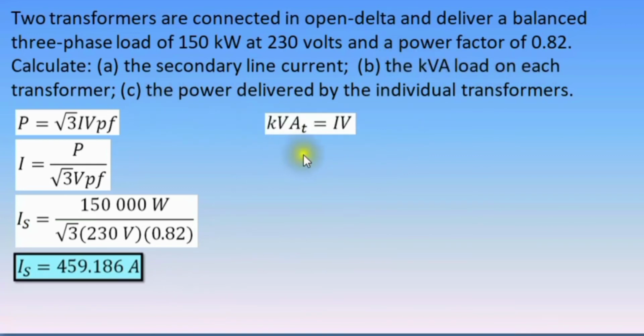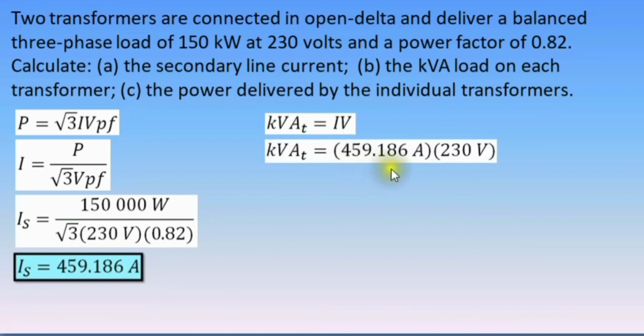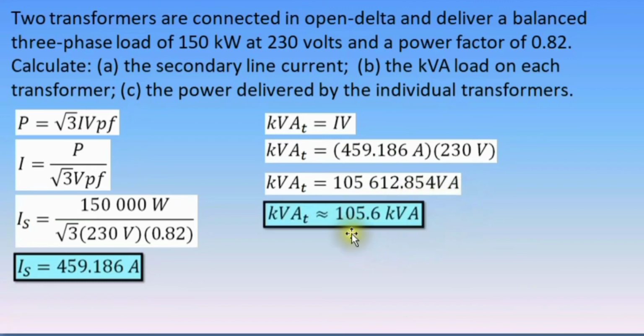For letter B, calculate the kVA load on each transformer. A simple formula, that is current times voltage. We already solved for the current, and the voltage is 230 volts. Substitute those values. We have 459.186 amperes times 230 volts. The answer is 105,612.854 volt amperes, or this is 105.6 kVA.